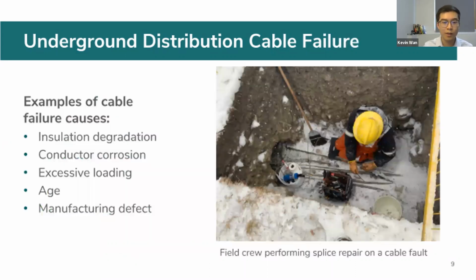And so there's a lot of speculation as to what's exactly causing these cable failures. There are common examples of these causes, which include cable insulation degradation, possibly due to exposure to heat, moisture, or dirt, conductor corrosion, again possibly due to moisture or water ingress, excessive loading causing stress and heat on the cables, age causing natural deterioration, and also possibly manufacturing defects.